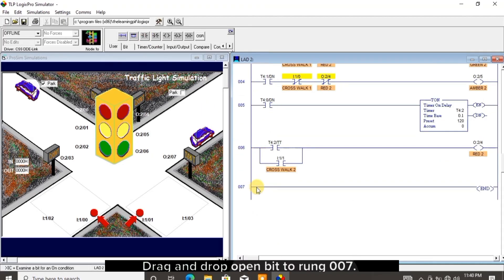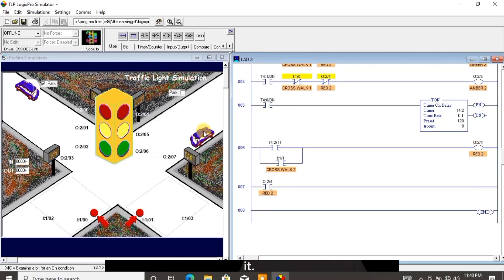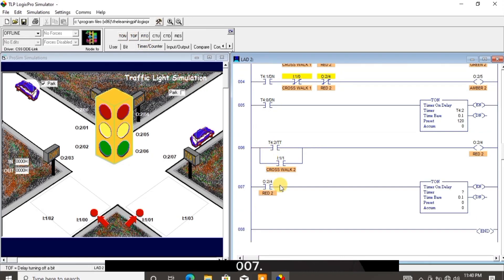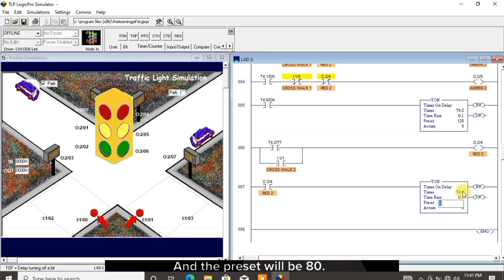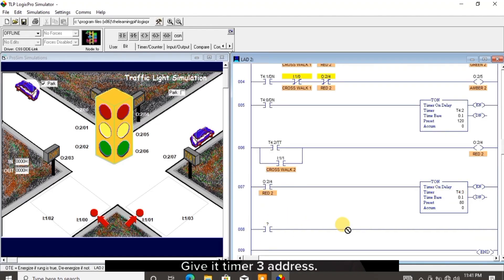Drag and drop open bit to rung 007 and drag and drop the red 2 address to it. I click on timer counter and drag and drop TON to rung 007. Make the timer address timer 3 and the preset will be 80. I click on bit. Drag and drop open bit to rung 008, give it the timer 3 address, and add /TT to it.